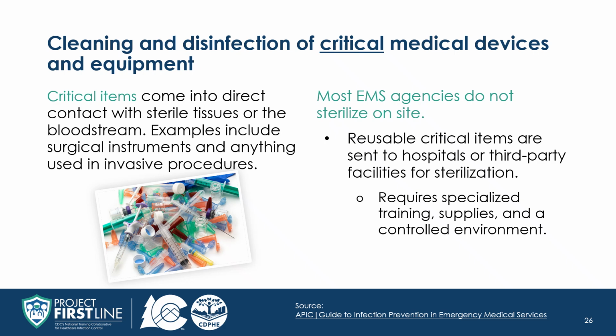Cleaning and disinfection of critical medical devices and equipment. Critical items come into direct contact with sterile tissues or the bloodstream. Since contamination of these items could lead to a serious infection for patients, they must be sterile before use. Examples include scalpels and forceps, to name a few. Sterilization of such items is generally not done on site. Reusable critical items are sent to a hospital sterile processing department or to a third party for sterilization.